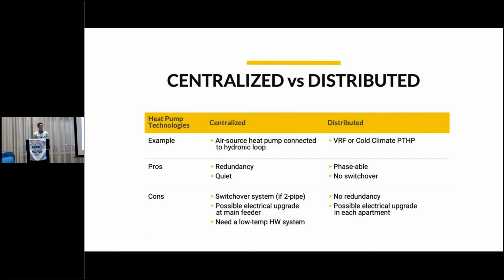On the other hand, you have a distributed heat pump system, where it's like a VRF system or a package terminal heat pump, where each space gets its own little heat pump. And the advantages of that are that you eliminate your seasonal switchover, because each space can operate its equipment as is. But the issue is that you remove that redundancy in your system. If that goes down, that apartment has no heating or cooling until you replace it. And then the other con is that each apartment then has to have the electrical capacity to handle that increased load. And so these are the two main systems.